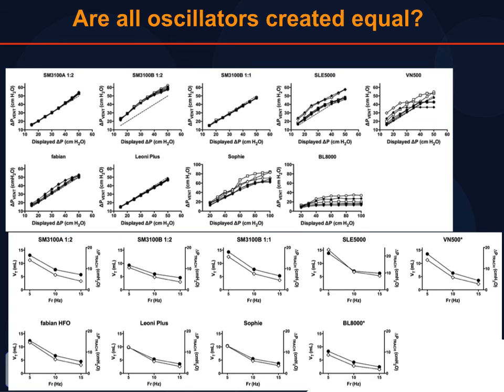As everyone knew, the BabyLog had this performance limitation in terms of the delta P it could generate, which doesn't necessarily translate to a clinical limitation. The VN was the one that interested us the most because we saw that at certain frequencies and ET tubes, so at frequencies of 5 and 10, the device was essentially linear, but at frequencies of 15, we saw that there was a loss of linearity at various delta Ps. There was a linear approach, and then it seemed to plateau out, at least in our test lung, and that occurred at a very high frequency with a 2.5 tube and 10 hertz, at a very high delta P, sorry.